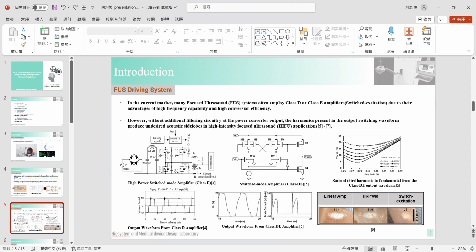Furthermore, over time, the surface of the piezoelectric ceramic in the transducer may be damaged, causing a shift in the central frequency. The output stage of the switched excitation amplifier forms a resonant circuit with inductance and capacitance, allowing only a very narrow range of frequency to pass. If the central frequency shifts, the output inductance and capacitance must be readjusted, which becomes more complicated and inefficient when applied to a multi-channel phased ultrasound system.